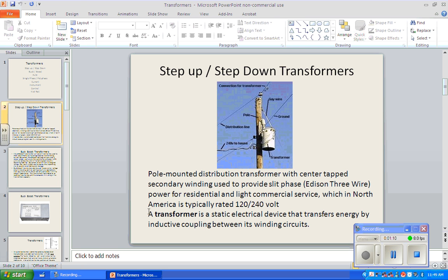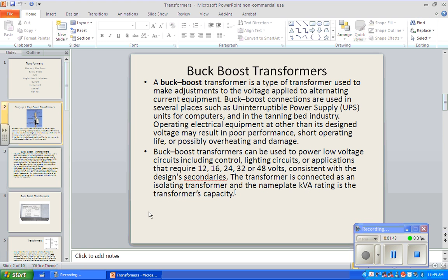And you'll notice how many wires are on this thing on the primary side. See the wires running across the pole? How many wires do you see? 2, that's correct. You have 2 phases. You only have 2 hot phases. How are they getting split phase 120, 240 out of that? They're creating a ground and grounding the center tap of the transformers to create a neutral conductor, a grounded conductor in between the 2 hot conductors that are related to both. And so that's our basis for our Edison 3-wire.